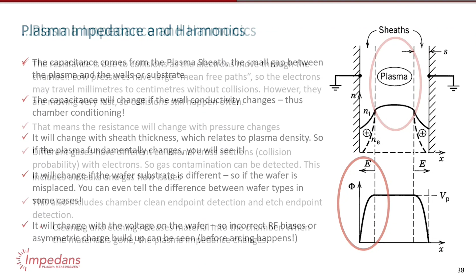I mentioned there's like a resistor equivalent. So if you imagine the electrons moving back and forth, they're going to collide with particles in the chamber. At low pressures, like under vacuum, electrons can travel millimeters to centimeters depending on the pressure, but they're moving fast, so collisions happen often. In other words, this resistance value will change with pressure changes. So if your pressure gauge is not calibrated correctly or if there's an air leak, you can actually pick that up using the sensor as well.